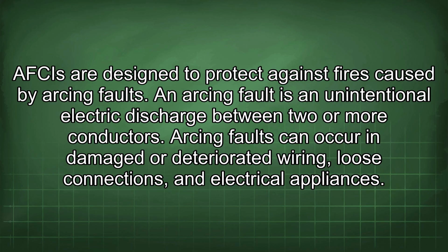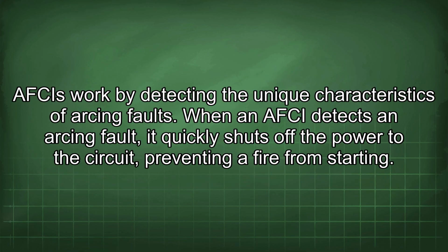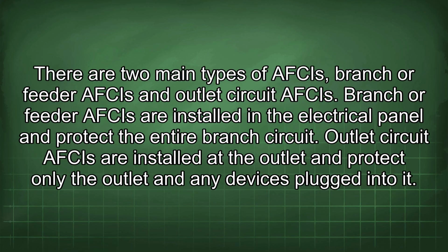An arcing fault is an unintentional electric discharge between two or more conductors. Arcing faults can occur in damaged or deteriorated wiring, loose connections, and electrical appliances. AFCIs work by detecting the unique characteristics of arcing faults. When an AFCI detects an arcing fault, it quickly shuts off the power to the circuit, preventing a fire from starting. There are two main types of AFCIs: branch or feeder AFCIs and outlet circuit AFCIs. Branch or feeder AFCIs are installed in the electrical panel and protect the entire branch circuit. Outlet circuit AFCIs are installed at the outlet and protect only the outlet and any devices plugged into it.